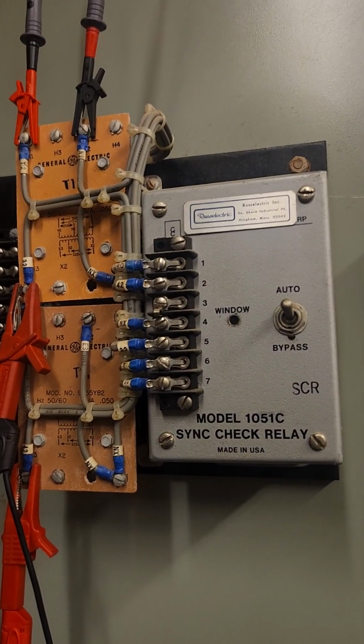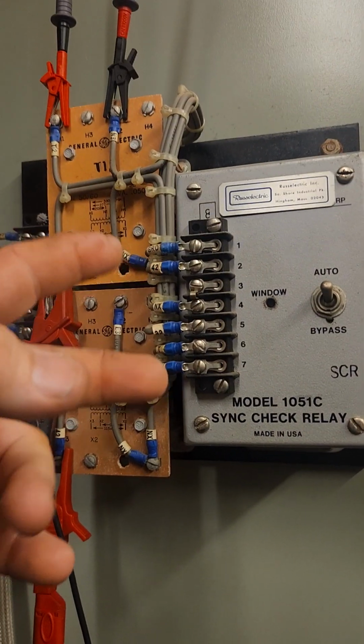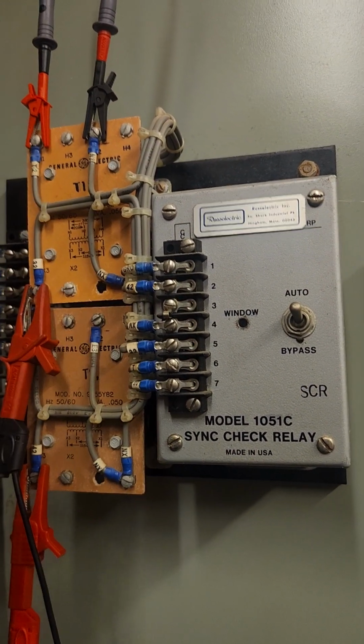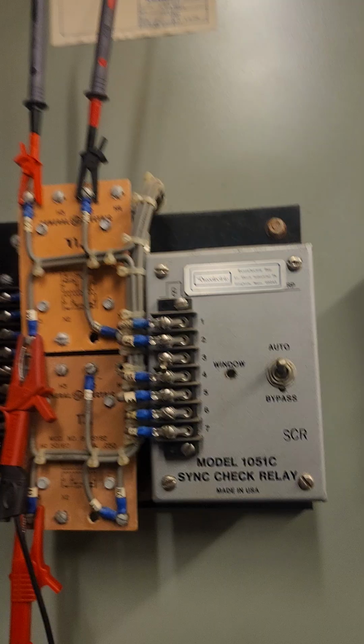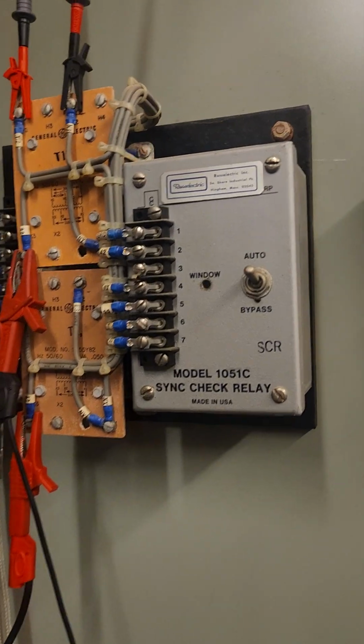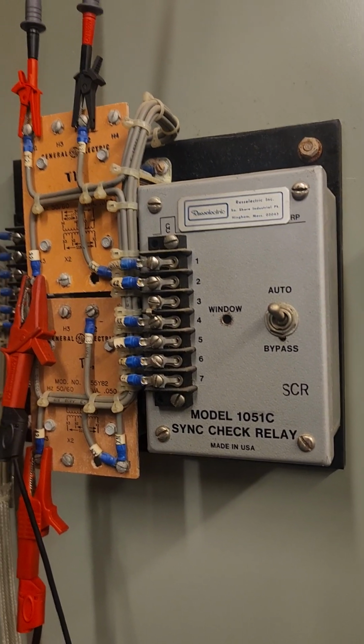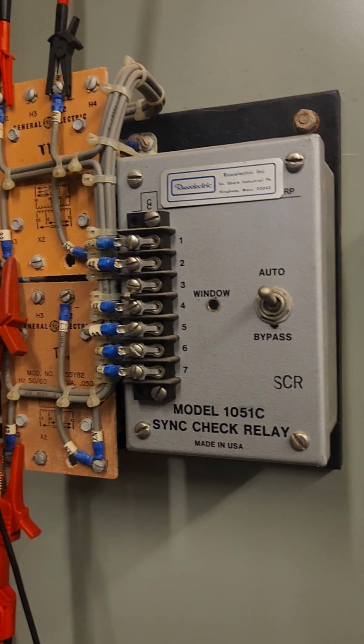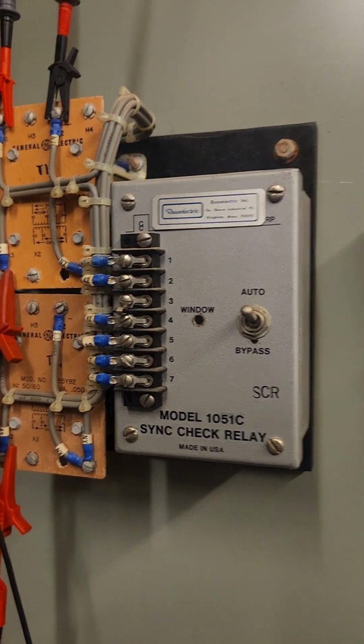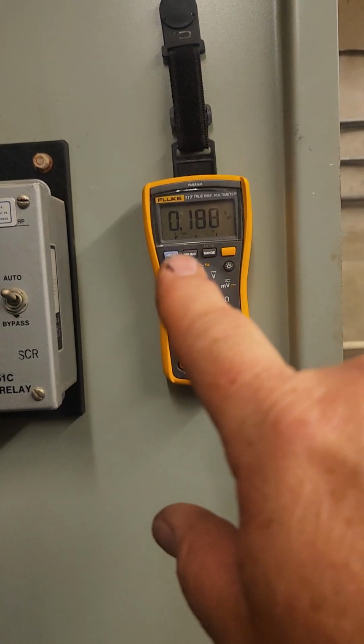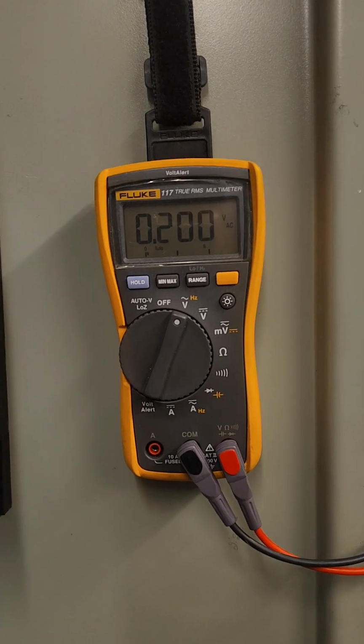So we made sure all those signals are present up to here, and if it's still not syncing, the other thing is the generator is 60, 61 hertz, and utility is 60, so it should come into phase pretty quick, and we've already measured it with the meter.